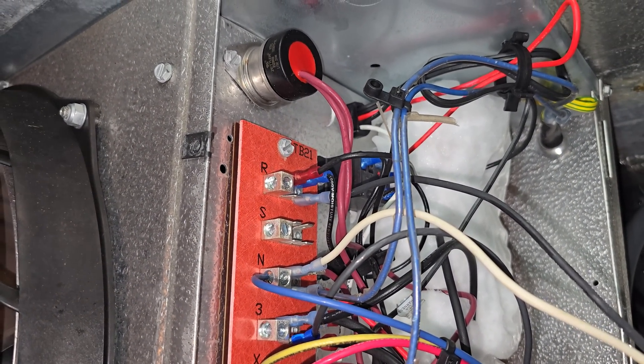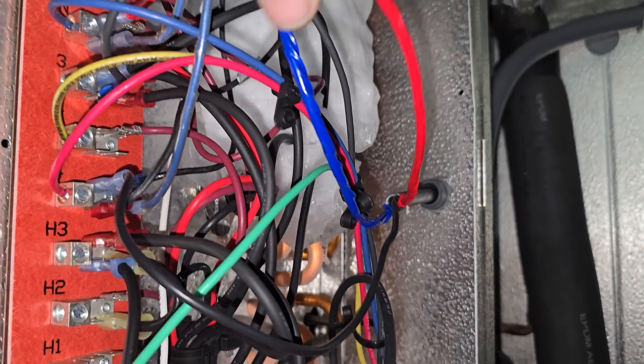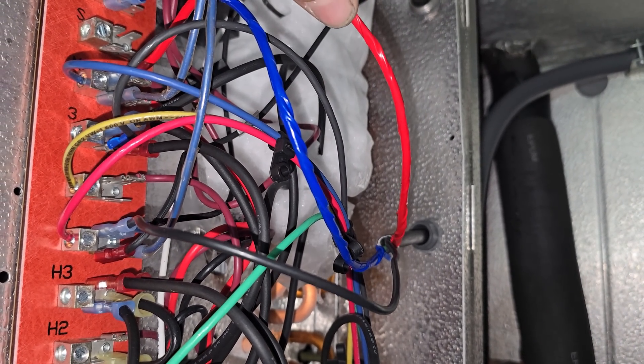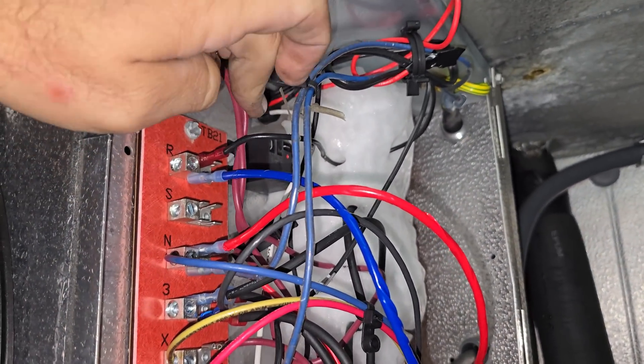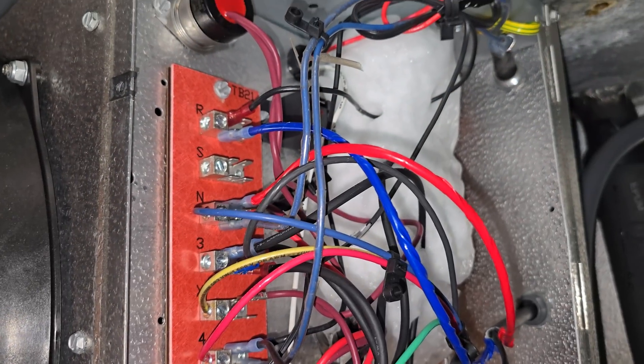We'll probably disconnect the two-speed fans too because I'm surprised they lasted this long. I cut it right here so I'd know where everything went — went from R to N, so they're just breaking the common or the N terminal. I got it wired in. I went in and taped the wires because I used three-wire cord with a ground, neutral, and black and white — re-identified them. Red is my N terminal, line two. Black is line one. Blue is my switch leg. I went ahead and disconnected that two-speed relay because it's going to be a problem — they tend to short out in the motor too. Disconnecting the relay gave me terminals for everything since I ran out. Now I just need a pump sprayer to get this little bit of ice out, then we'll get this thing turned on and tested.